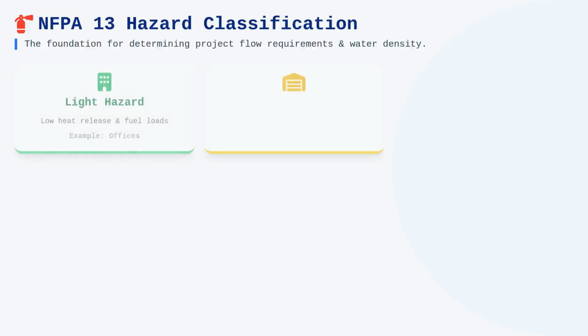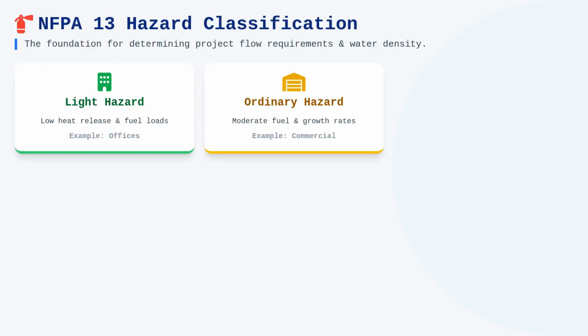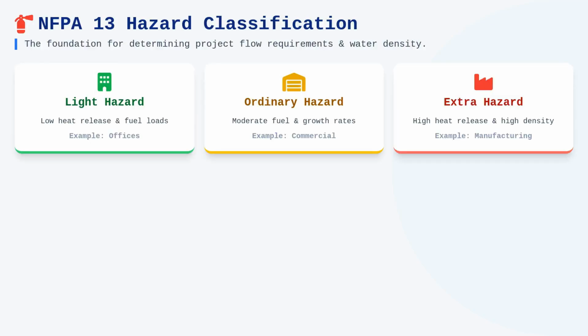Understanding the hazard classification is your first step in determining the flow requirements for a project. NFPA 13 classifies spaces into light hazard, ordinary hazard, and extra hazard, each with distinct fuel loads and growth rates. For a light hazard occupancy like an office, the expected heat release is relatively low, while extra hazard classifications, such as those found in manufacturing or processing facilities, require significantly higher water densities to achieve suppression or control.